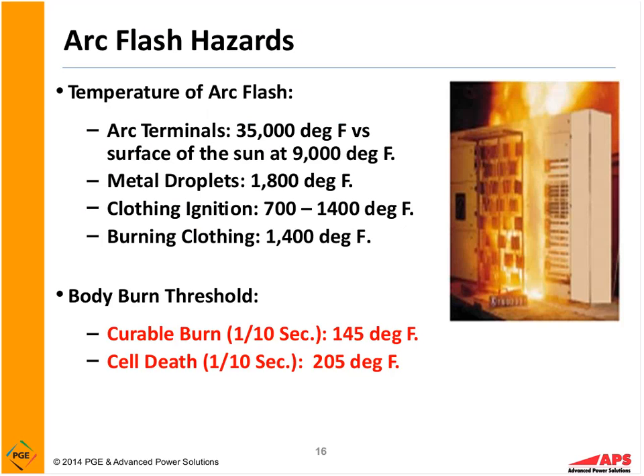So metal droplets coming off the arc we could see burning upwards of 1,800 degrees, the superheated metal. Clothing ignition: if that heat hits your clothing, between 700 and 1,400 degrees Fahrenheit, your clothing can catch on fire. And burning clothing can burn upwards of 1,400 degrees. Now compare that with what your skin can handle. A curable burn for a tenth of a second, 145 degrees. Cell death, 205 degrees. Is there a big difference there between the heat that's coming off the arc and what your skin can handle? Absolutely. This is why it's absolutely essential we pay attention to arc flash and to protecting yourself and your personnel against arc flash hazards.